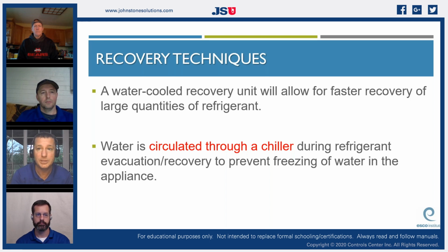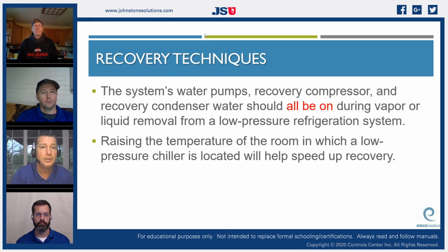And then it won't freeze because it's not stationary long enough to freeze. Same principle. Now, if we look at the system's water pumps, recovery compressor and recovery condenser water should all be on during vapor and liquid removal from a low pressure system. Same thing. Raising the temperature of the room in which a low pressure chiller is located will help speed up the recovery. And I've seen them do that.